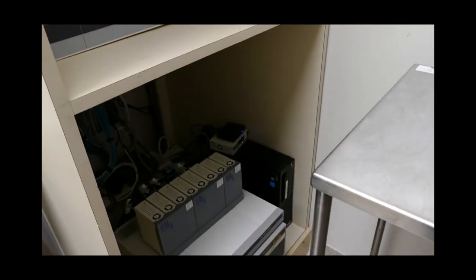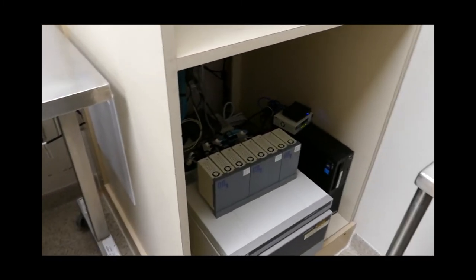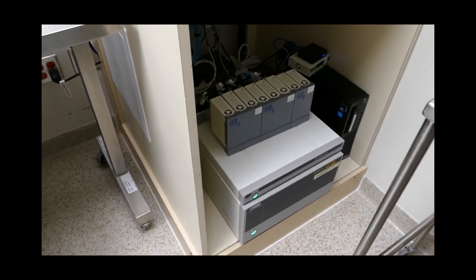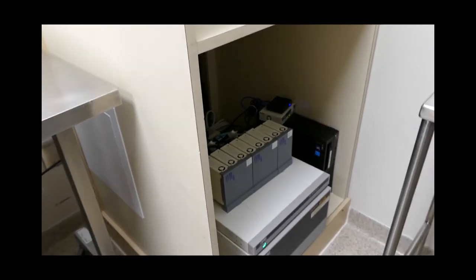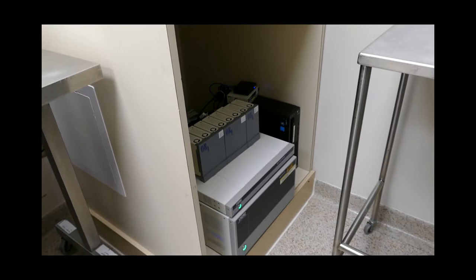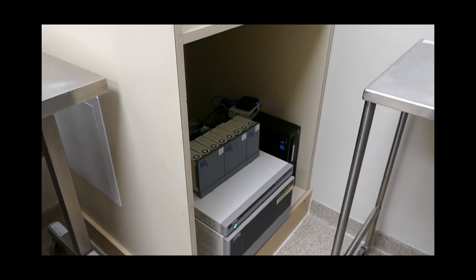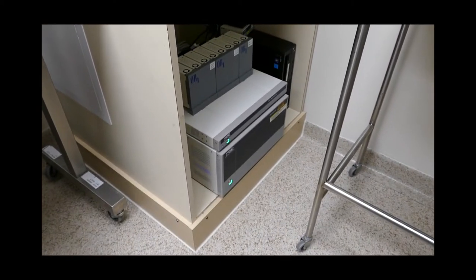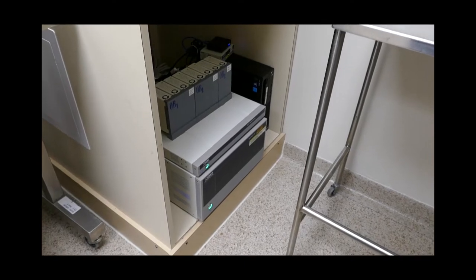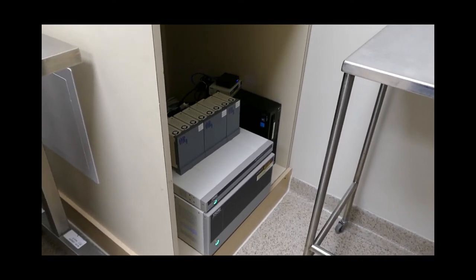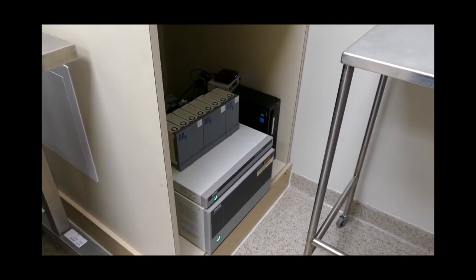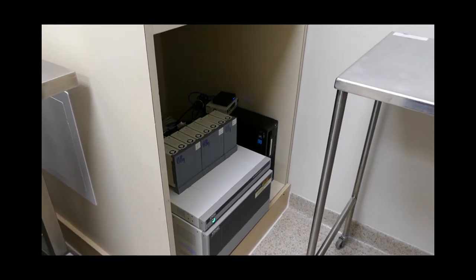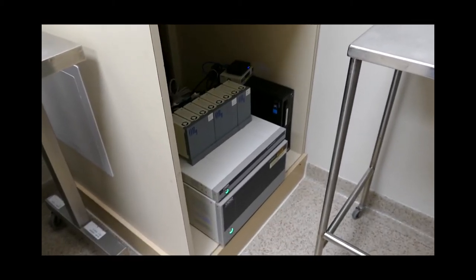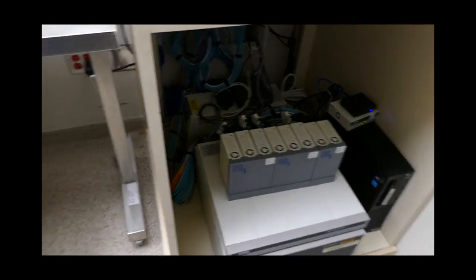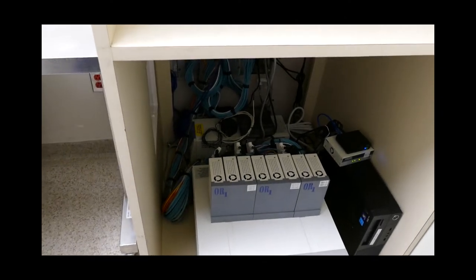Let me see if I can get this out of the way. I don't know if I'm too happy with this. Actually, I'm not happy with this. The old system used to be in a rack and it was contained, it was safe. You can see, even though the installers here were excellent people, I'm not too happy that the system itself isn't integrated into a rack. So it has no place to really sit except down there on the bottom. Anything that sits on the ground, of course, gets dirty.